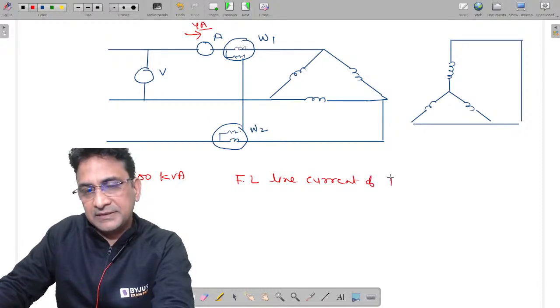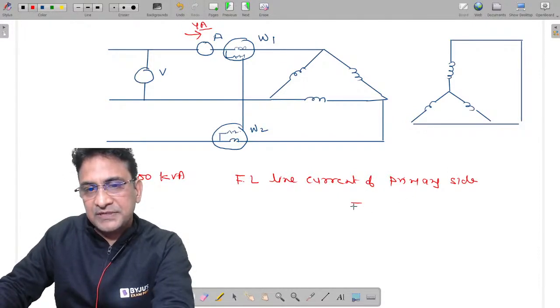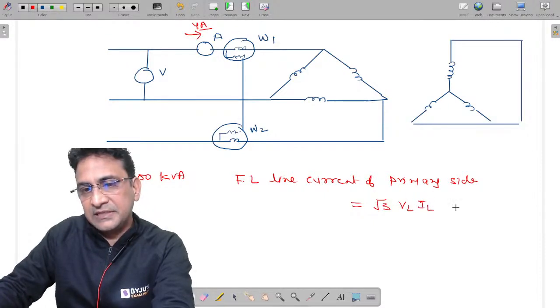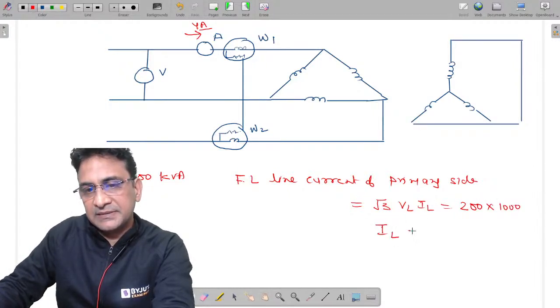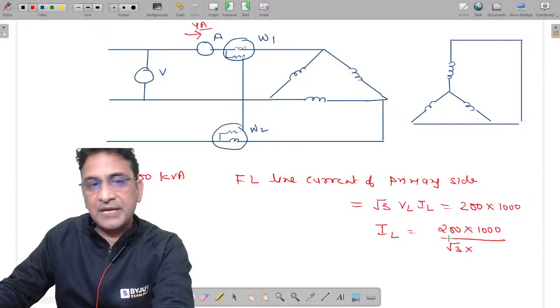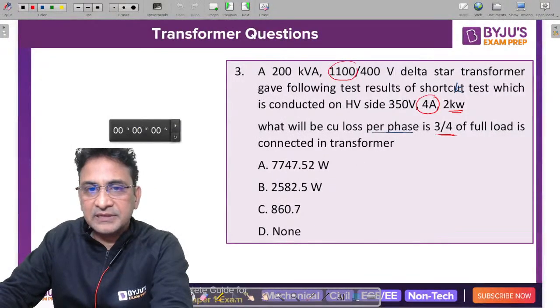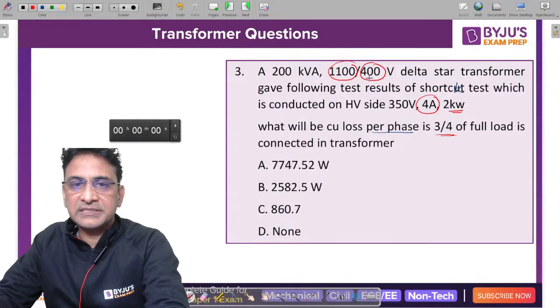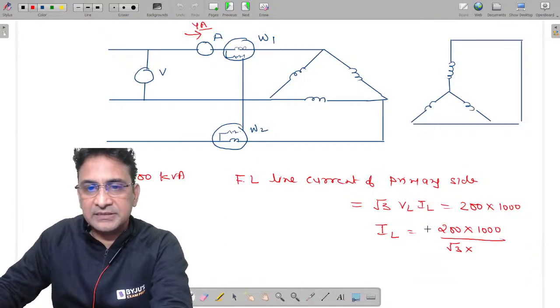What is the full load line current of the primary side? What is the three phase kVA? Three phase kVA is nothing but root 3 V_L multiplied by I_L. This is the three phase kVA and it is equivalent to 200 kVA, that means 200 into 1000. So what will be the line current? 200 into 1000 divided by root 3 into line voltage. This is my line voltage. In the three phase rating, the voltage or current given is always the line voltage and the line current. So it is the 1100.